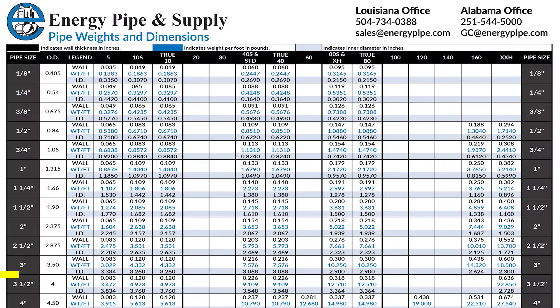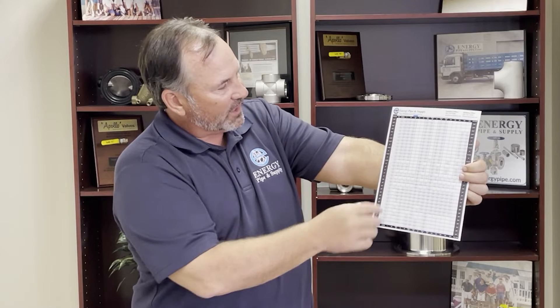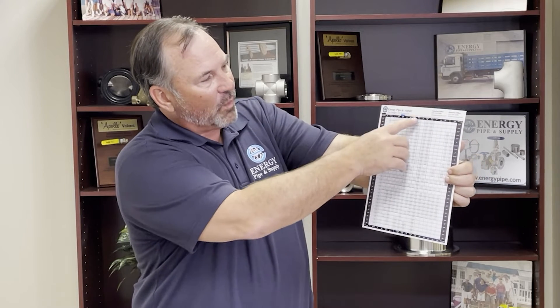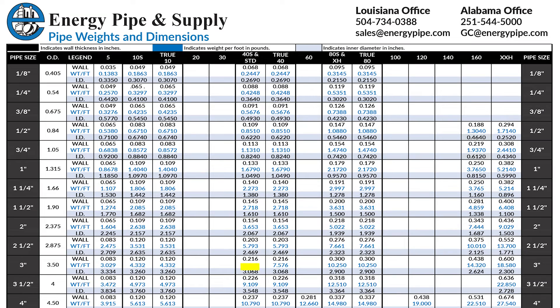It'll also give you an ID and the wall thickness. So let's break down what you're looking at when you're looking at a pipe chart. For three inch pipe, the next column is going to show you exactly the outside diameter, which is the OD on the pipe chart. It'll also give you the wall — so for standard wall or schedule 40S, it's going to give you that wall thickness. And then underneath there it will give you the ID of that pipe, which means the inside diameter.